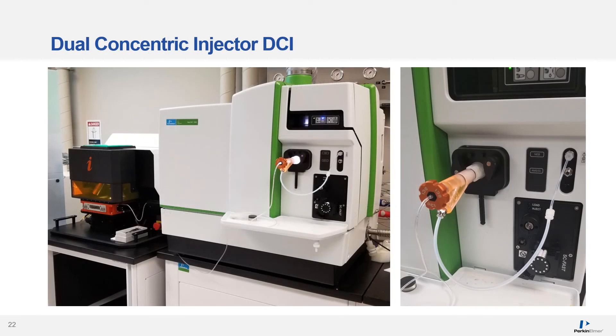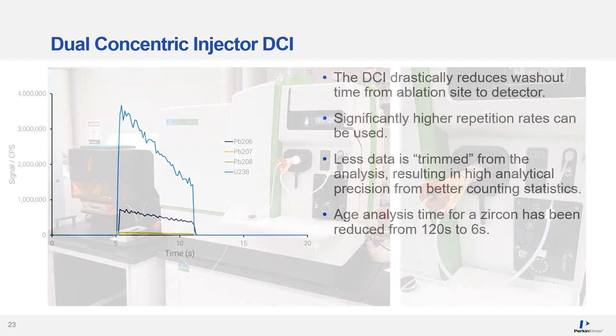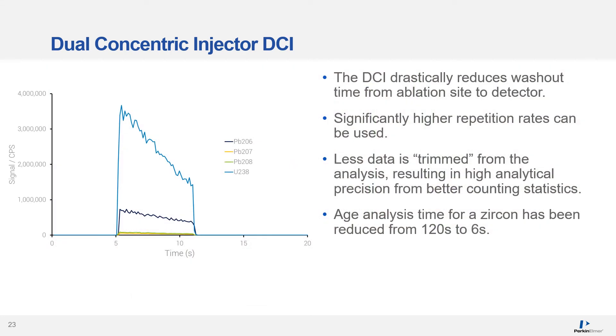Another update to the laser ablation ICP-MS offering is the Dual Concentric Injector, or DCI, shown here installed in the NexION 2000 ICP-MS. It has been designed to have a minimum dead volume and space for particle deposition leading to the injector of the ICP-MS. The DCI reduces washout significantly — by reducing this washout from ablation to ablation, less data is trimmed from the analysis and a considerable reduction in analysis time can be gained. In this example, you can see a 6-second ablation, whereas prior to using the DCI the ablation time was about 120 seconds to do the same zircon dating.